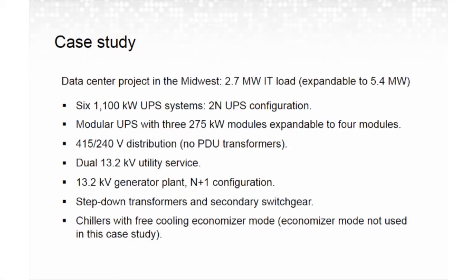So what we're trying to do is take that transformation and push it as close to the load as we could. There are step-down transformers and secondary switchgear. Just to note, this is a building with chillers. It does have economizer mode to get some free cooling. In this case study, those economizers were not utilized. So just for a note.